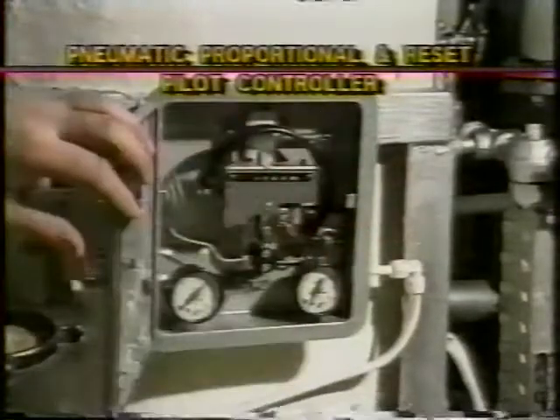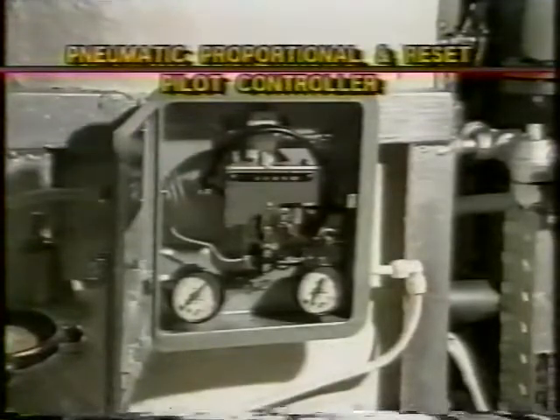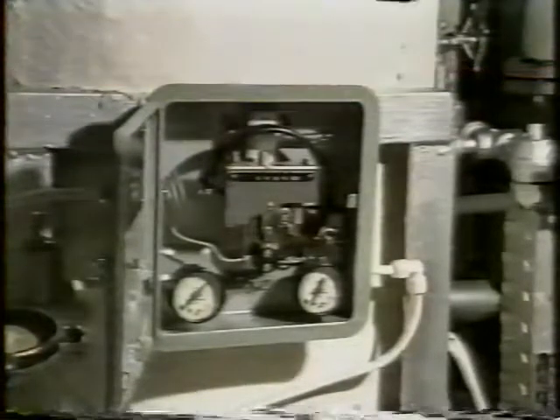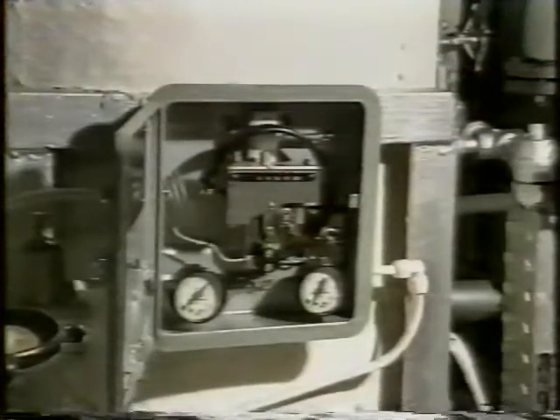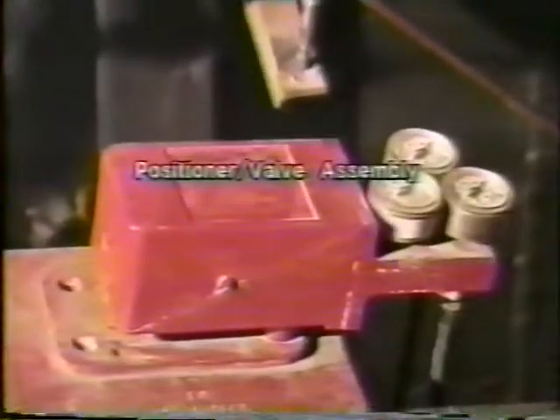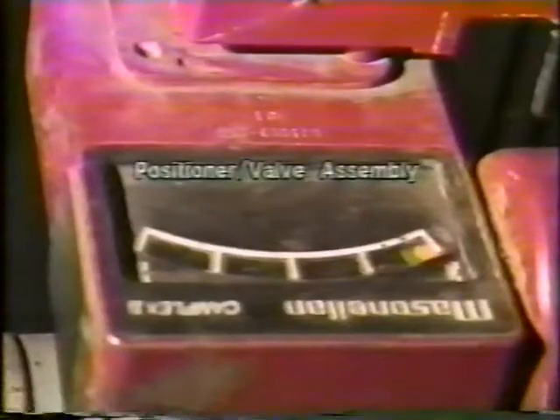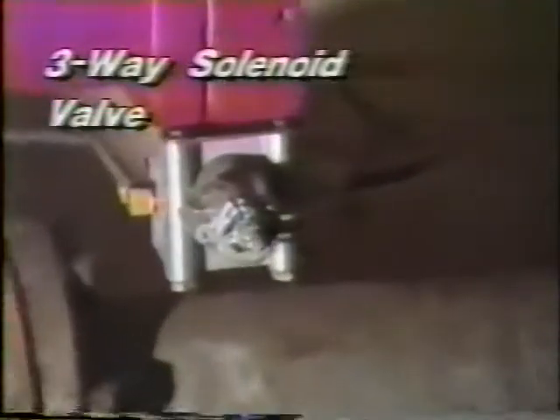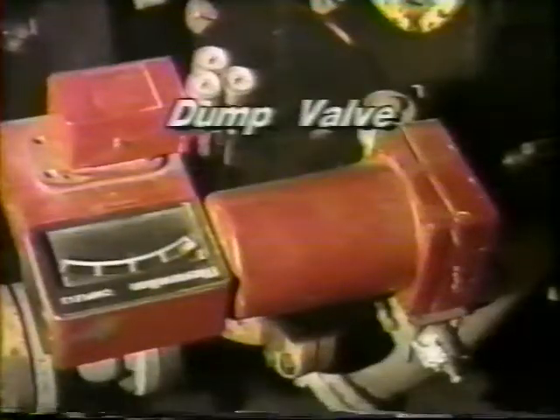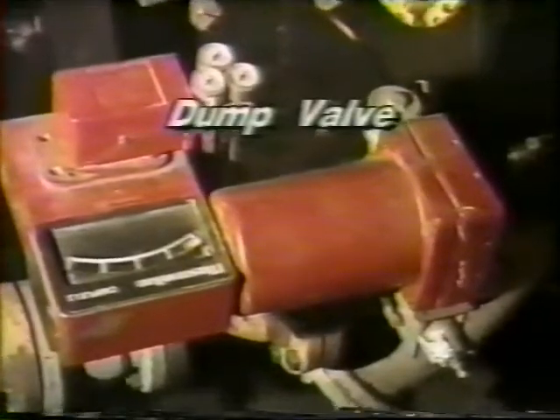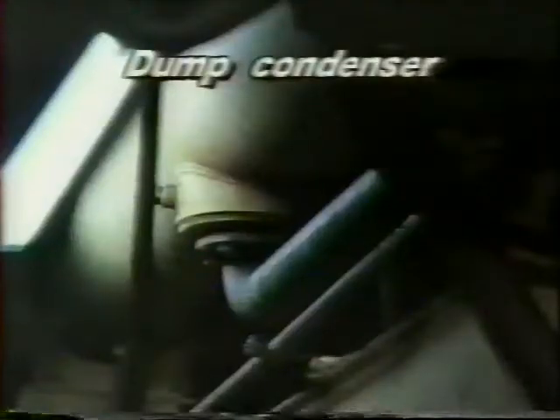This action is accomplished through the pneumatic proportional and reset pilot controller mounted at the steam separator, which sends a pressure signal to the positioner valve assembly to open or close the valve. A three-way solenoid valve is included to close the dump valve upon loss of signal from a pressure switch in the cooling water line to the dump condenser.